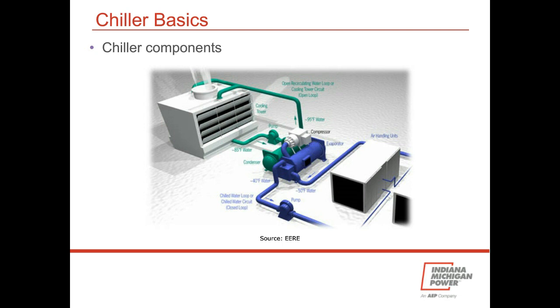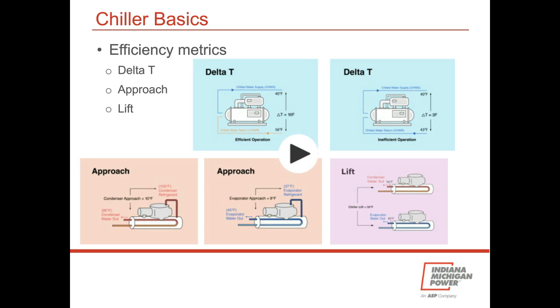You have on the right-hand side the chilled water loop, and it's showing about a 40-degree supply and a 50-degree return, so a 10-degree delta there. And then you have the cooling tower loop, showing again a 95-degree supply to that cooling tower and an 85-degree water return. So again, about a 10-degree drop as well. And there are a number of efficiency metrics that are important for chillers, and I've listed several here: delta T, a couple of approach temperatures, and lift. High chiller efficiency is accomplished by properly controlling a lot of energy-munching chiller subsystems like the refrigerant loop compressors, the water loop pumps, chiller evaporator fans, cooling tower condenser fans, air handling fans, and they all affect these metrics.